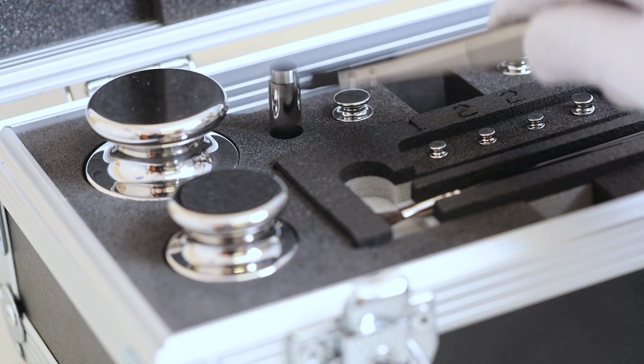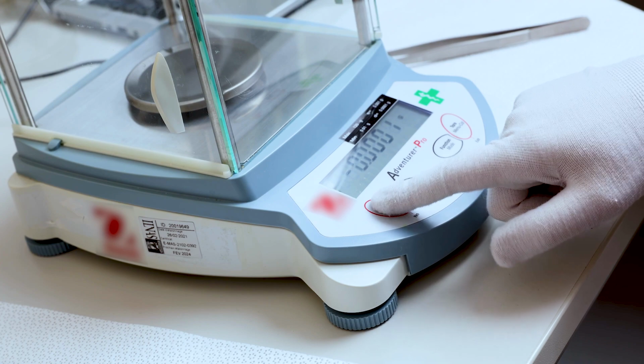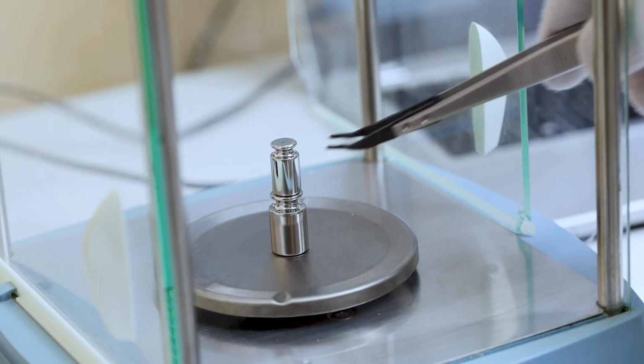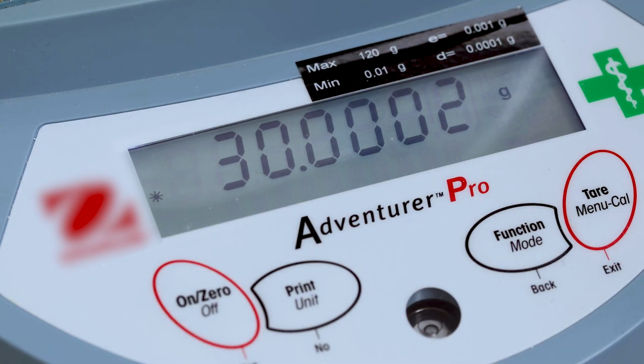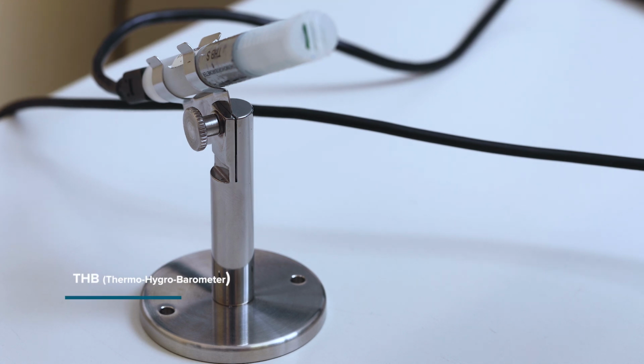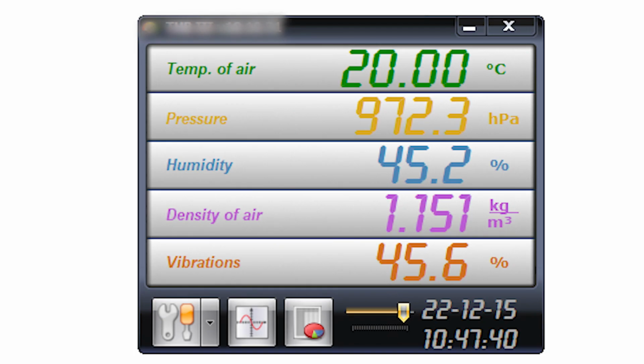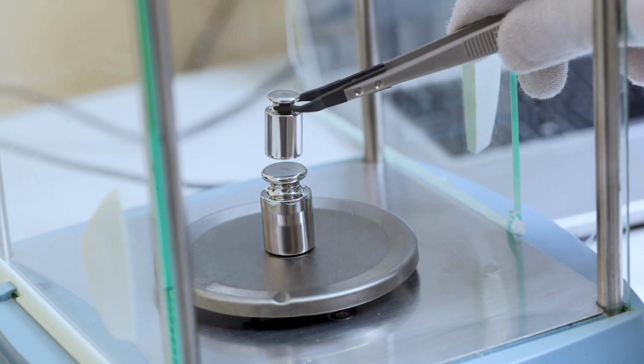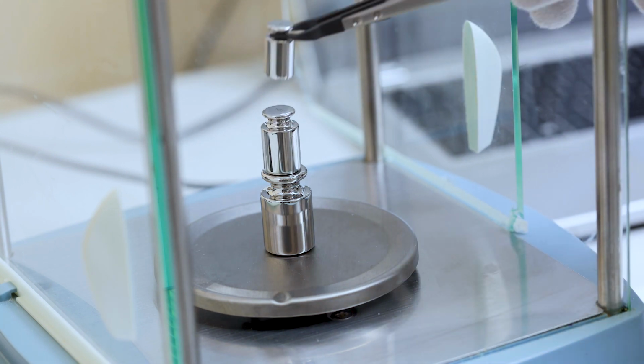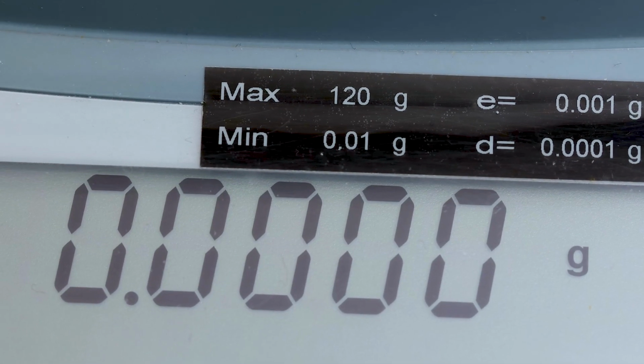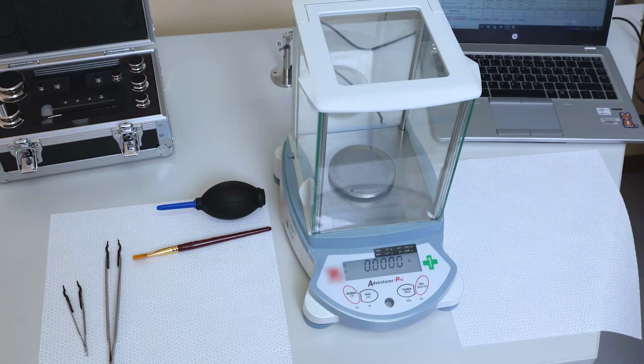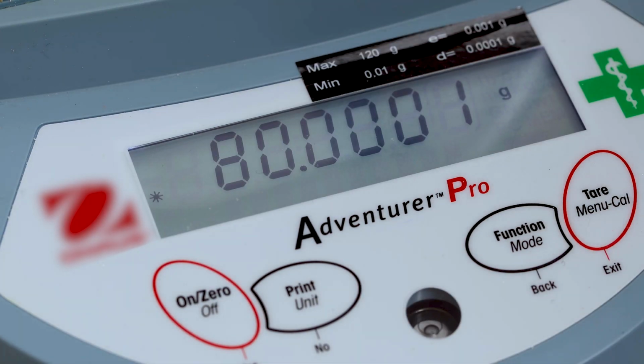The operator, equipped with weights adapted to the scale, here of Class E2, will be able to start the calibration by checking the linearity of the scale. In addition, he has a THB sensor, thermohygrobarometer, allowing him to measure the ambient conditions. He places the weights gradually on the weighing pan in order to cover the entire range of the scale. To determine the accuracy error of the scale, the value without and with the weights must be taken into account.